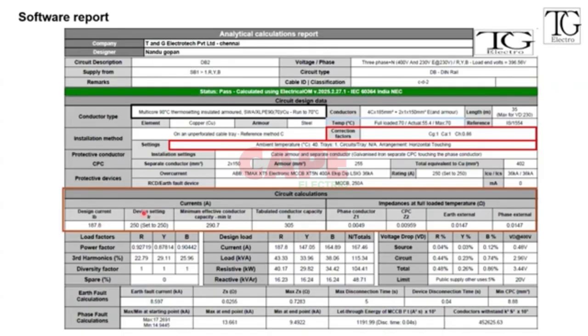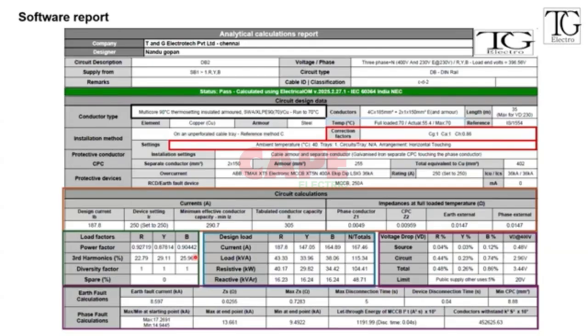What device you are going to keep, what device setting you are going to keep, what is the minimum effective conductor capacity, and what is the current carrying capacity. You'll also get load factors, the percentage harmonics expected, the design load, the voltage drop at that location, and also the earth fault current and the phase fault short circuit current. You'll get all those exact calculations considering all the correction factors, the reactance, multiple sources, and multiple parallel paths like armour and GI strips. So this is what is required.